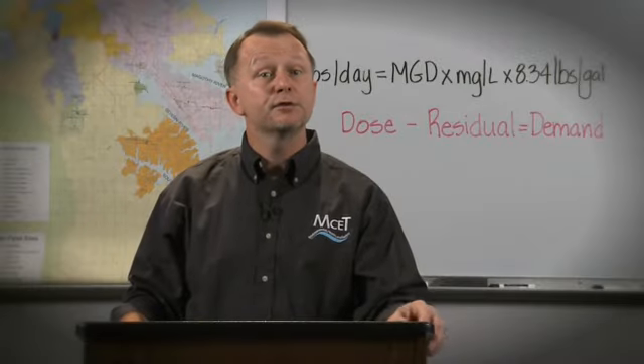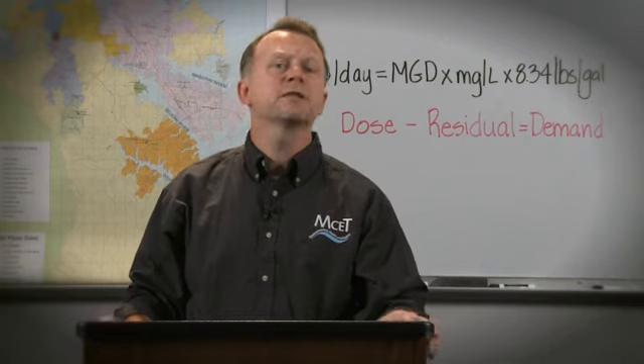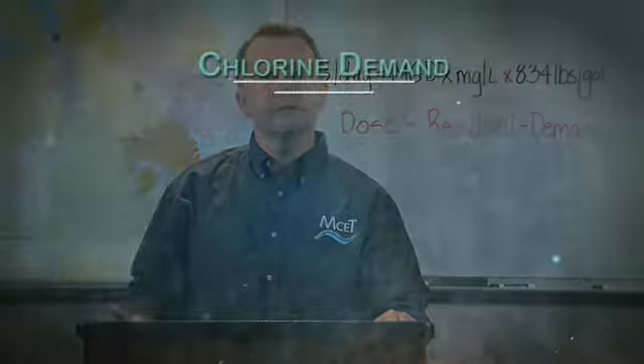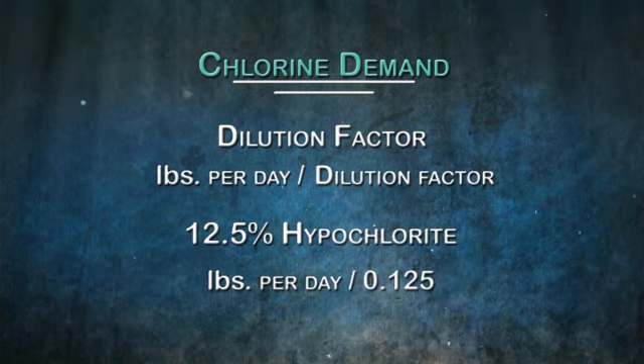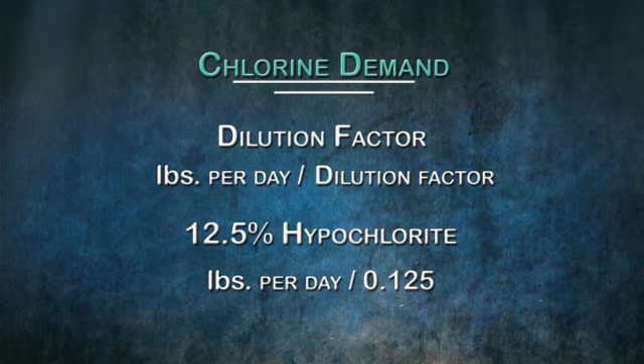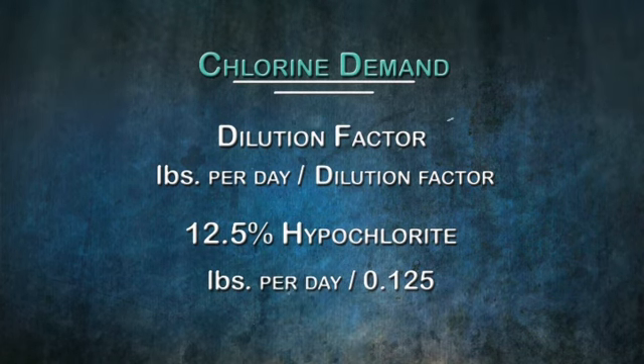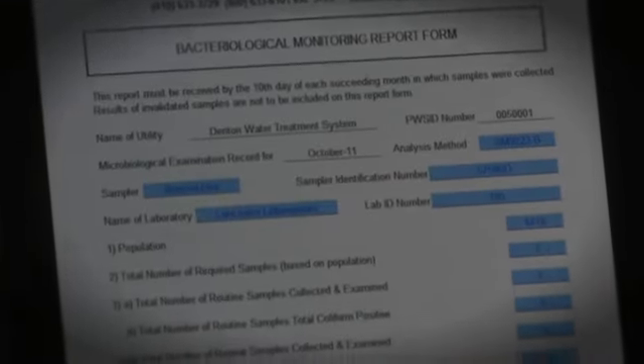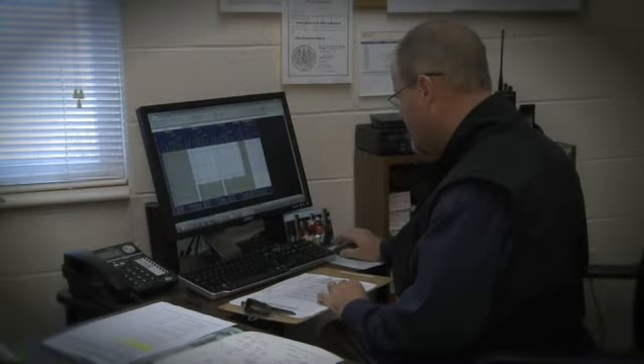Because the formula is for straight 100% chlorine, a dilution factor must be applied when using sodium or calcium hypochlorite. Simply divide the pounds per day by the dilution factor. For example, if you are using 12.5% sodium hypochlorite, then you would divide the desired pounds of chlorine by 0.125 to obtain the pounds per day of sodium hypochlorite required to produce the same dose. As previously discussed, good monitoring and record keeping practices are essential to maintaining adequate disinfection. In addition to the results of chlorine residual and bacteriological monitoring, the water system operator should record the total amount of chemical that is applied to the water each day.